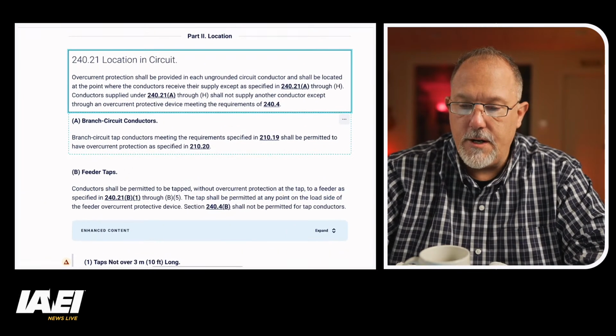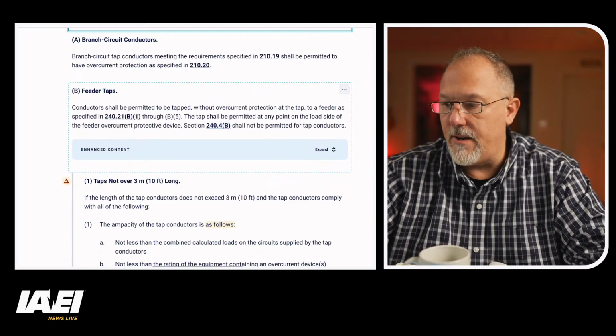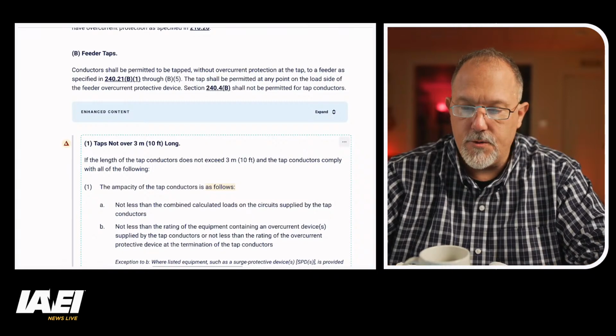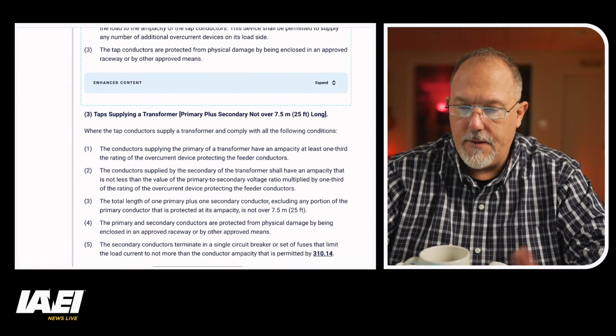rules, and that's in Article 240, specifically 240.21, at your location in the circuit. So that's where you're going to find your feeder taps and the requirements around a feeder tap. You have your rules for taps not over so many feet long. You got 10 foot, you got 25 foot, and then you have your transformer tap supplying a transformer, etc. So what you have in 215 is the permission to tap a feeder and which feeders you're allowed to tap, and then once you do that tap, now you're into Article 240 for where the overcurrent protection is in regards to that tapped conductor and what are the rules around that. So 240.21 is going to be your reference there.